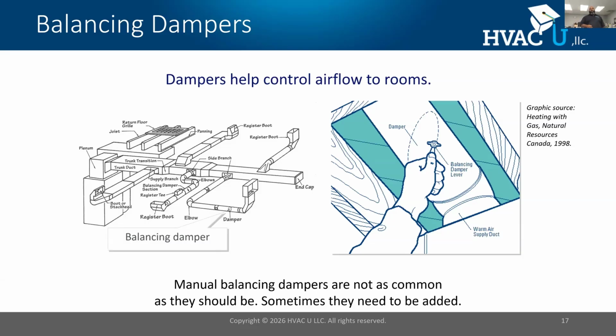So we have to do balancing. When we do balancing, we're going to test it in a heating mode and cooling mode. And then we identify on the dampers the position of that airflow where it's going to be marked at. All right, guess what? You can't balance a system if it's not properly sized. You can't, the duct system, if it's not properly sized. And you can't size a duct system if you don't have a load calc done.